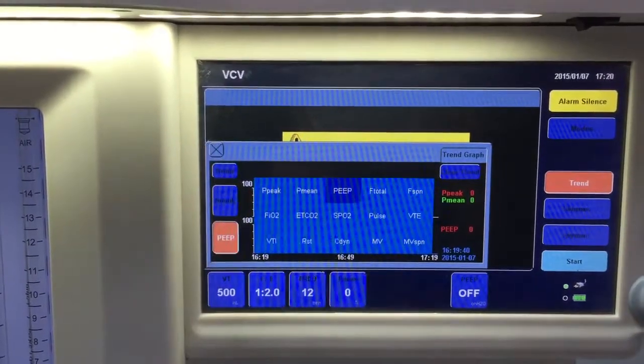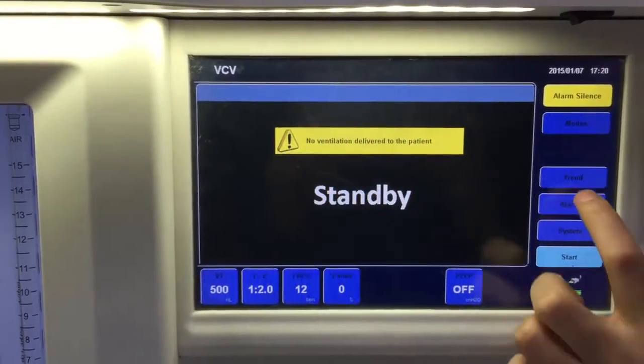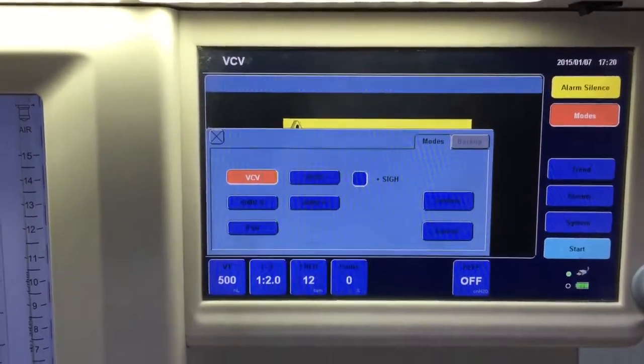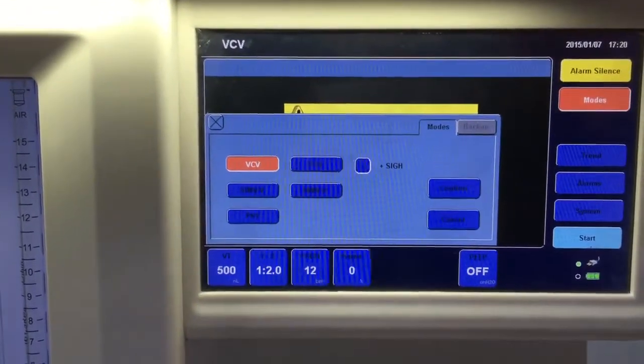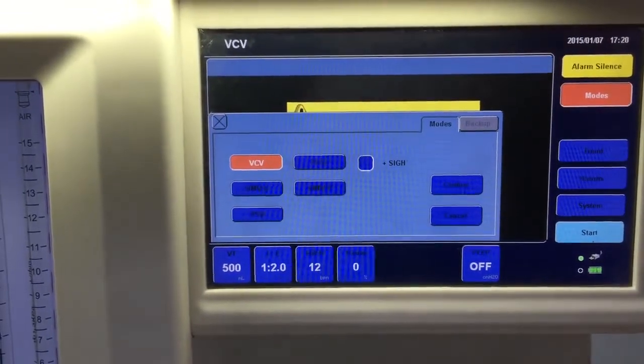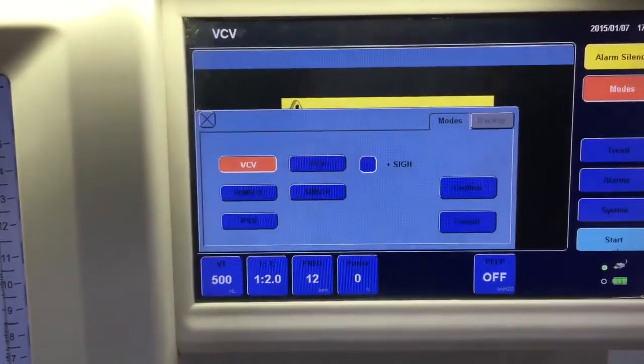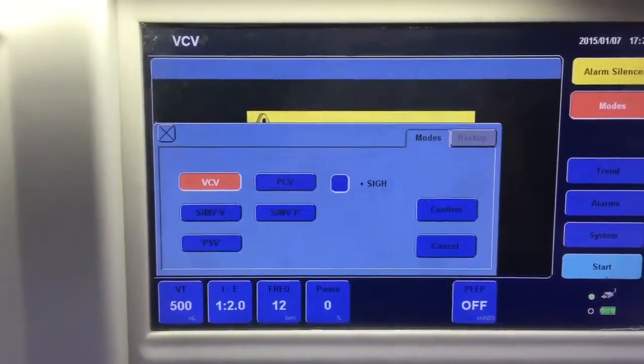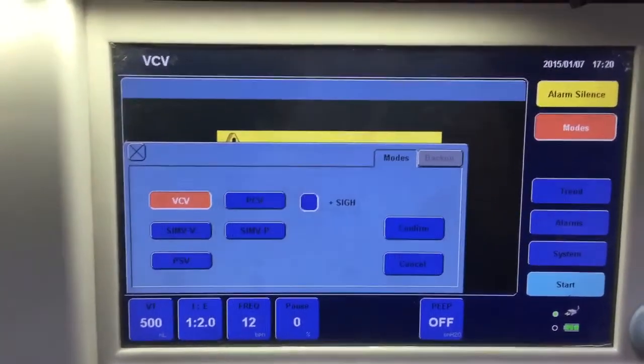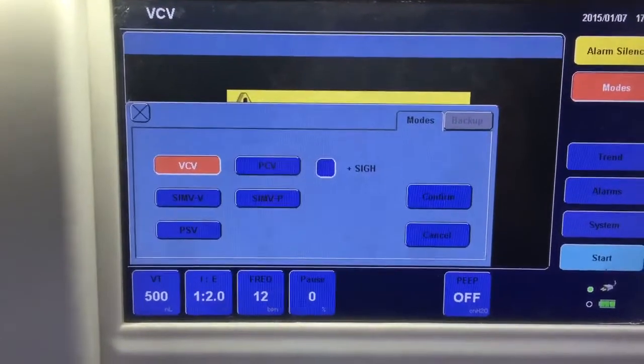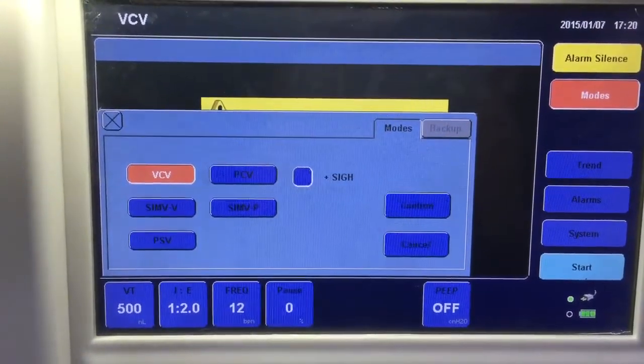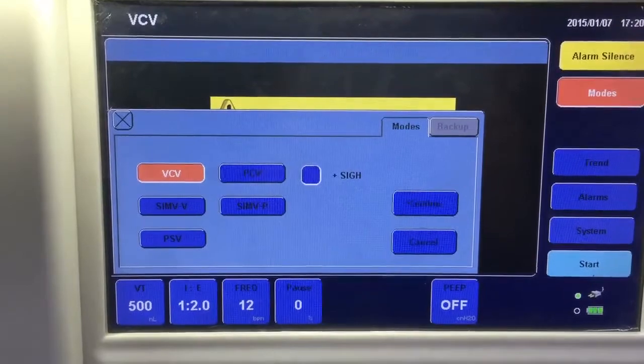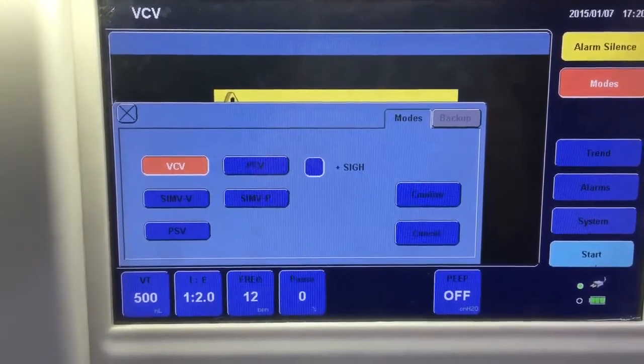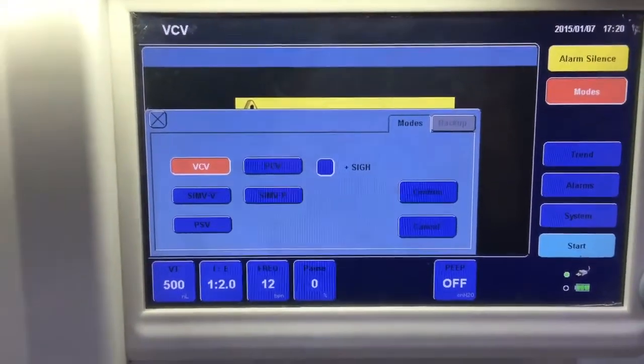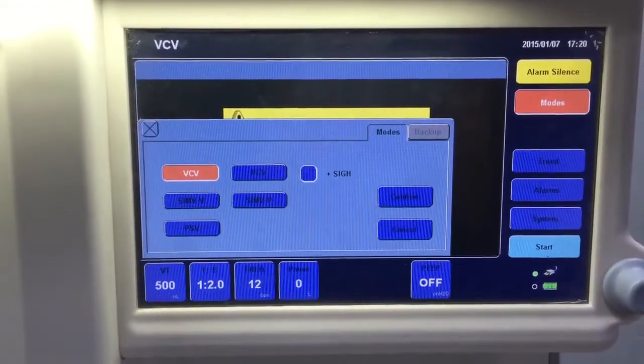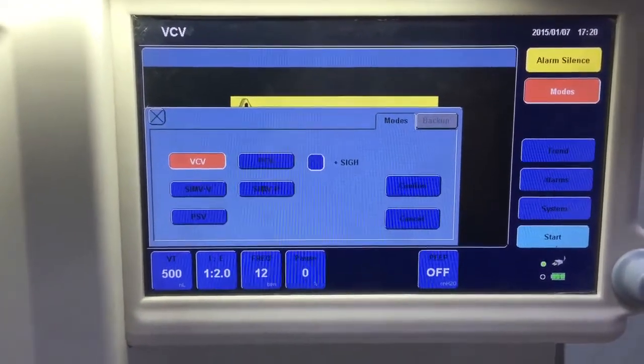For ventilation, we can also have different modes. For now, we configured PCV, VCV, and also SIMV-PS. And PRVC is available here. In the machine we may call it PCV-VG, which is pressure control volume guaranteed. We can also offer that option. So we can upgrade the whole machine to high-end to meet most, maybe 99% of operation use.